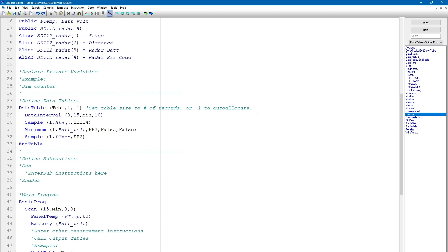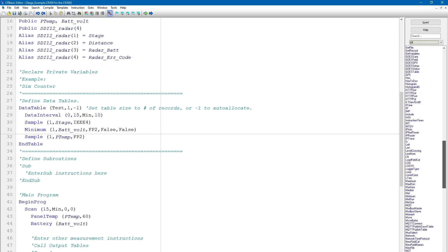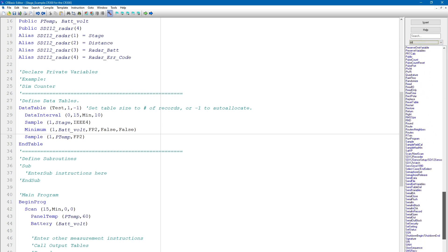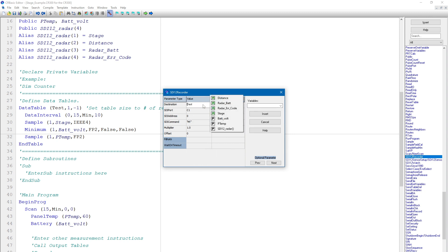Now that I have defined the program variables and configured the data table, I will go into the main program section and add a stage measurement. Place the cursor on the line below the battery measurement and add the SDI 12 recorder measurement. Now go over to the instruction list and double-click on the SDI 12 recorder instruction. This opens a parameter window for this instruction. In the destination parameter box, I will right-click to view a list of all the variables in the program. In this case, I will select the SDI 12 radar variable array since the SDI 12 recorder instruction will report all four sensor outputs.